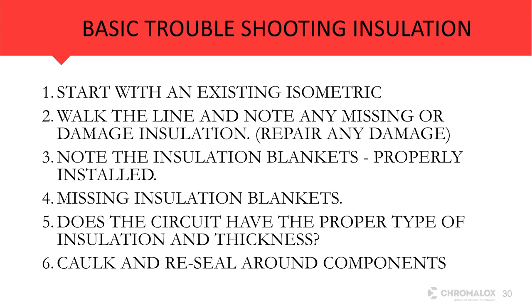Does the circuit have the proper type of insulation and thickness? Make sure you caulk and reseal around components. A lot of times clients will go back and do work on heat tracing. They'll strip off a section of a line and just put back on whatever insulation they have instead of trying to follow the guides on the heat tracing isometric. The problem with that is that insulations have different types of heat loss. So you need to be careful going back, if you do work, to put back the proper insulation and thickness that's in the design.